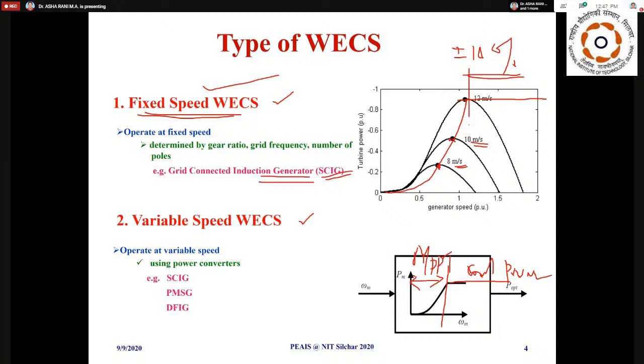This MPPT region cannot be used in the case of a fixed speed wind energy conversion system; only the constant power part can be used. Whereas in variable speed wind energy conversion systems, there is also SCIG but with a different configuration, and we also have permanent magnet synchronous generators and doubly fed induction generators.